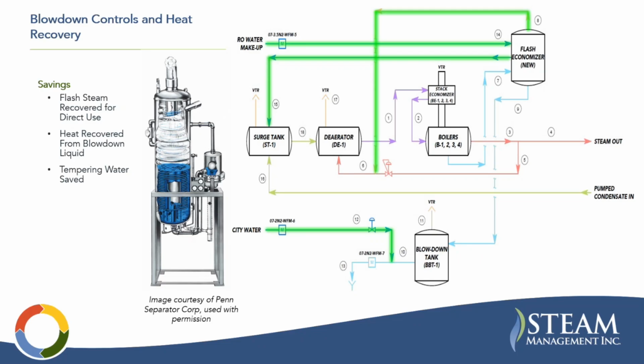So in this scope, you have the surface blowdown coming to a heat recovery system. In this system, first, the blowdown is going to flash off. That steam flashes off clean and can be reused in the deaerator. So it's going to offset some of the steam requirement here. Then there's going to be some sort of heat exchanger, either internal to the flash tank or downstream. But you're going to typically use that to preheat makeup water.